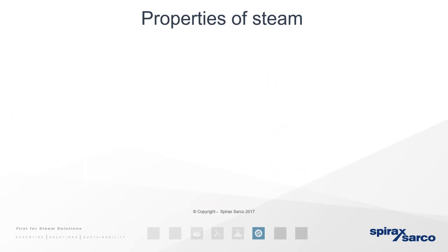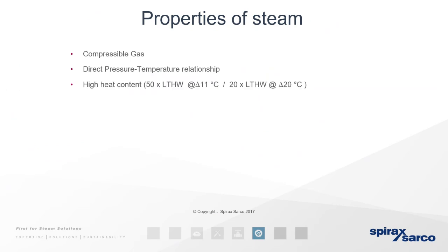So properties of steam. Why do we use steam? It's a compressible gas, which means you can make pipe work smaller, depending on pressure, of course. Direct pressure and temperature relationship. So the higher the pressure, the higher the temperature, which means that it's an increase in enthalpy. So the latent heat, or the energy, that will be given to whatever you're heating or using. And it's higher heat content than hot water systems. So as you can see there's the figures with delta T's. In this particular case, you've got 4.19 kilojoules per kilogram of water, and you have 2,200 kilojoules per kilogram for steam.